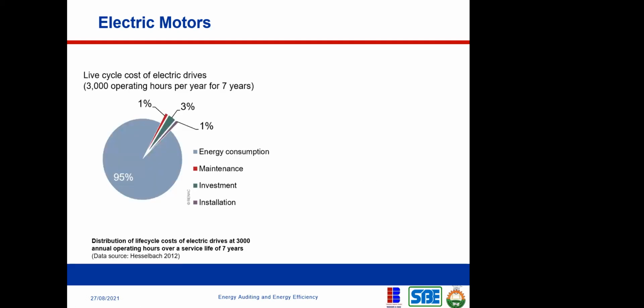So, electric motor life cycle cost. The life cycle cost of the electric motors, assuming that the motor is operating for like 3,000 hours per year and it operates for about 7 years. Putting this assumption into perspective, you're going to see that the energy consumption cost of that motor is 95% for that 7 years. So the capital cost that you use in buying that motor is almost insignificant, 3%.